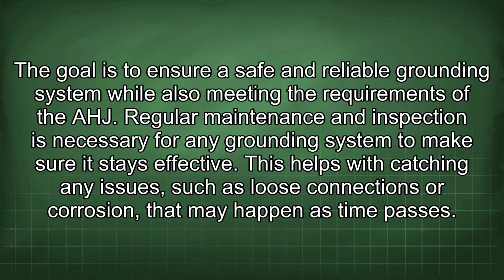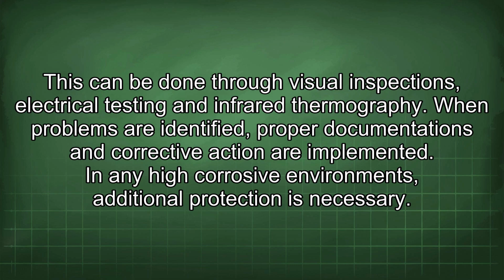Regular maintenance and inspection is necessary for any grounding system to make sure it stays effective. This helps with catching any issues, such as loose connections or corrosion, that may happen as time passes. This can be done through visual inspections, electrical testing, and infrared thermography. When problems are identified, proper documentation and corrective action are implemented.